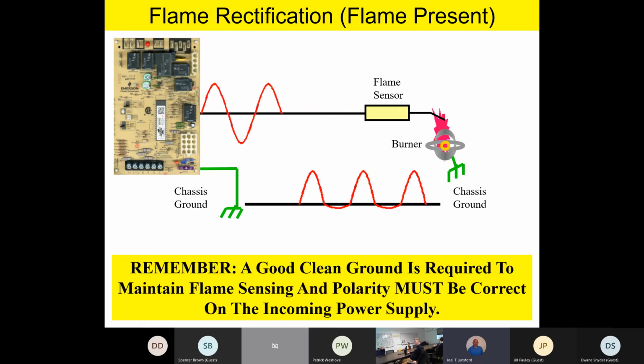Now, it should be noted, one of the things that's really, really important, again, you have to have a good solid ground. You have to have a good ground to that furnace, and the flame sensor has to be clean. In addition, the polarity on the furnace has to be correct. In other words, if your neutral and your hot wire are reversed on your power coming in, the board is not going to be able to see the fire, so to speak, because of polarity. So polarity has to be correct, good solid ground all the way to earth ground, and then a clean flame sensor. Those are very, very important in order for our flame sensing circuit to work properly.